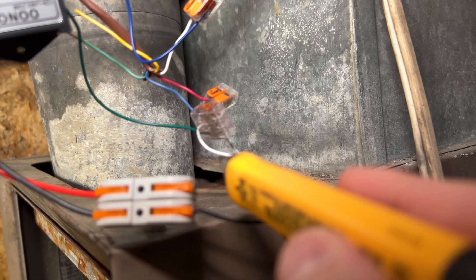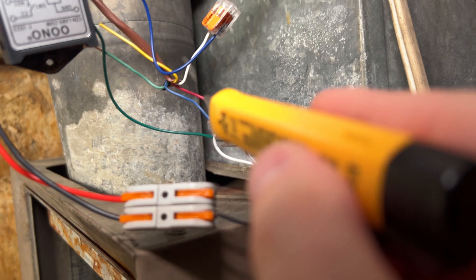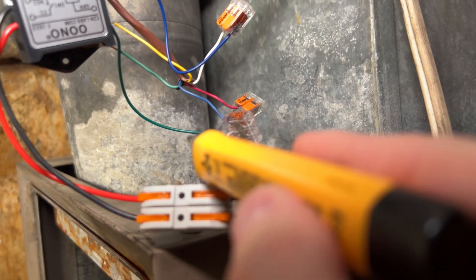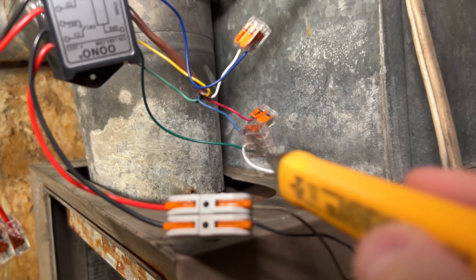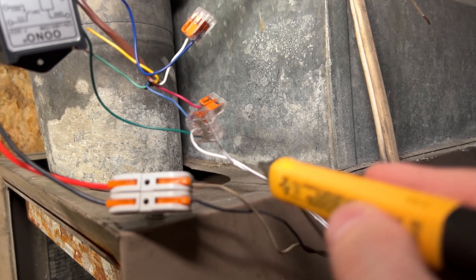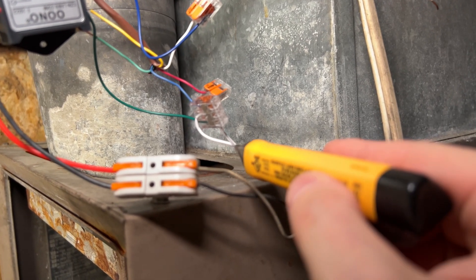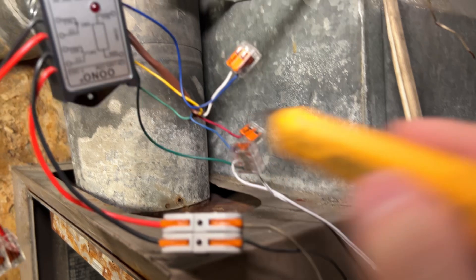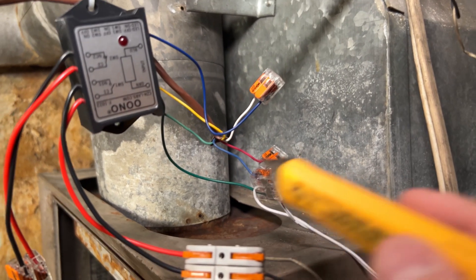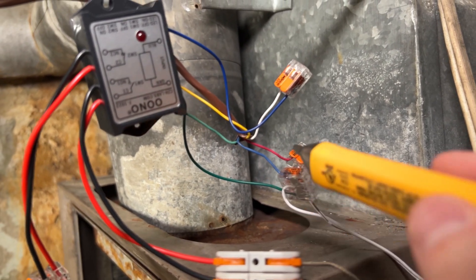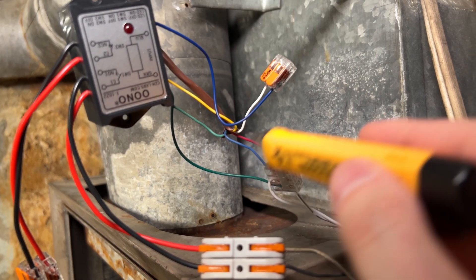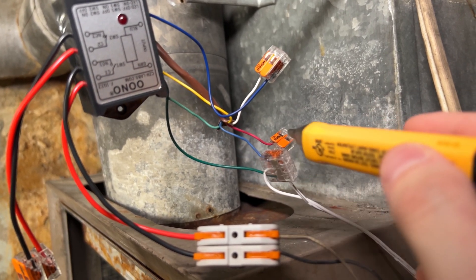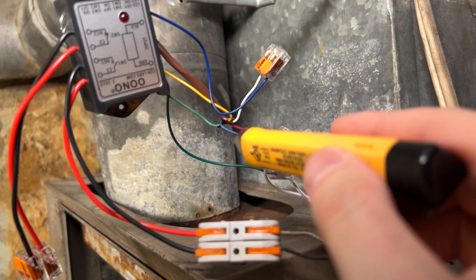So incoming power gets split: one side goes to C, one side goes to our relay. It doesn't matter which one of these wires we use, either of these white wires from the power supply. It's AC so it doesn't matter, there's no polarity here. And that's our red and blue or R and C, so that's how we power the thermostat.